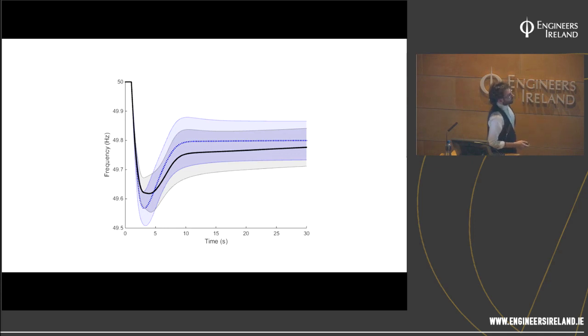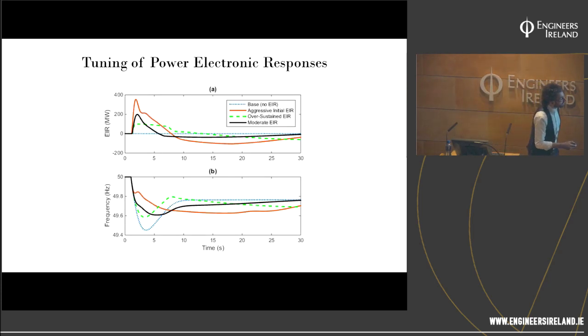I suppose points to note: the maximum rate of change of frequency wasn't impacted, but what it can do is minimize the deviation. What these controls can also do is push out your time to nadir. So for example, if you compare the blue and the black there, with these controls you can push out that time to minimum frequency as well.